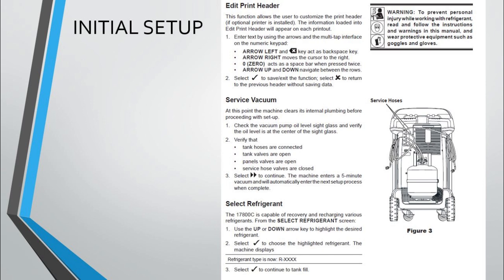From the Select Refrigerant screen, 1. Use the up or down arrow key to highlight the desired refrigerant. 2. Select Check to choose the highlighted refrigerant. The machine displays "Refrigerant type is now R-XXXX." 3. Select Check to continue to tank fill.